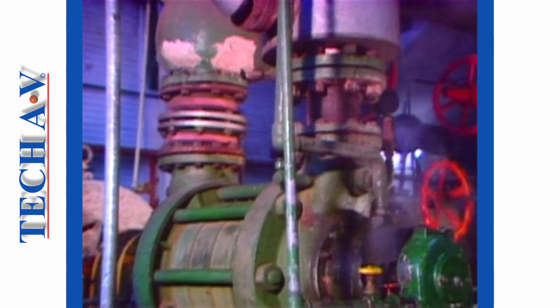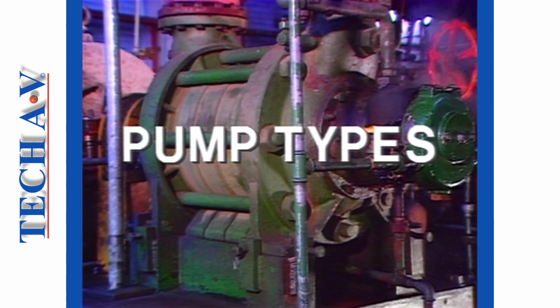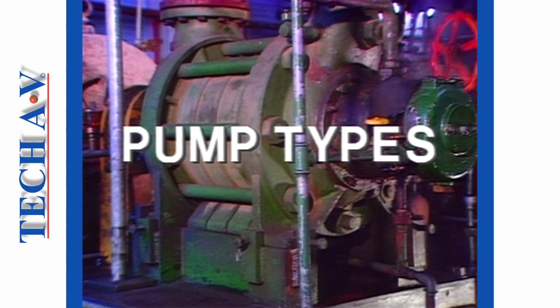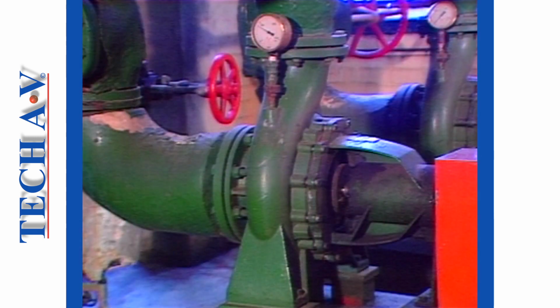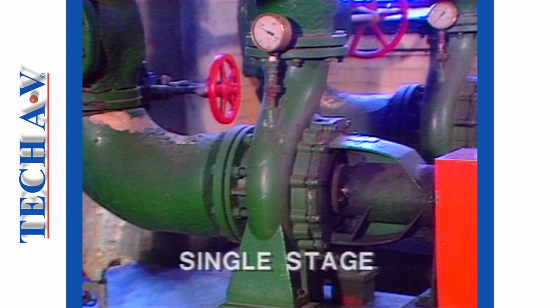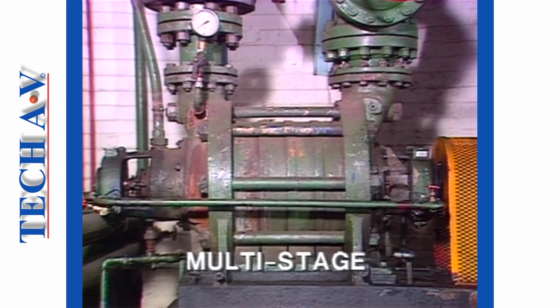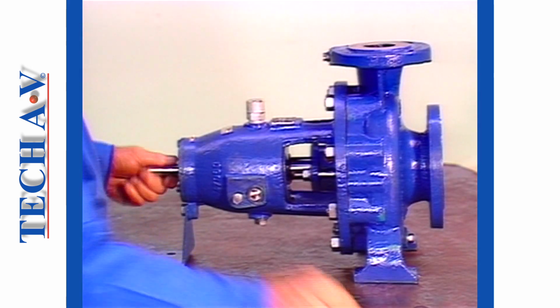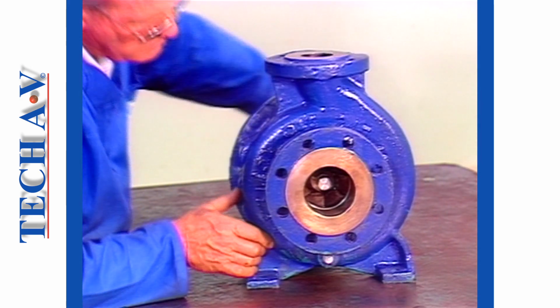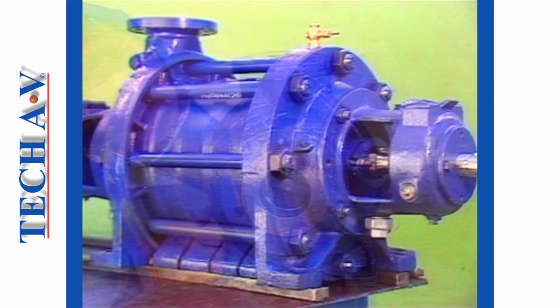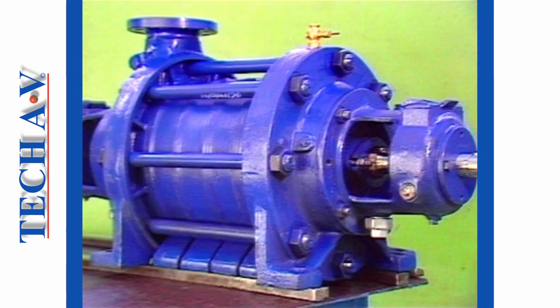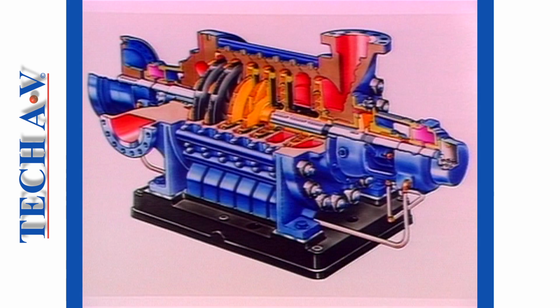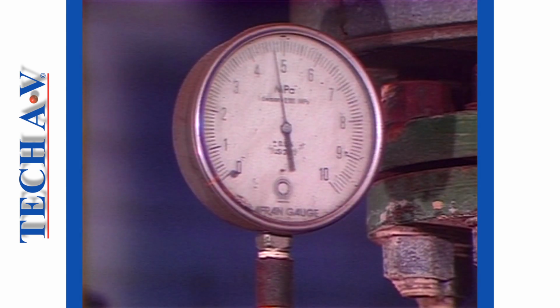We return to discuss some of the centrifugal pump types that you are likely to encounter in general industrial areas. To make a general categorization, there are two main classifications of centrifugal pumps, namely single stage and multi-stage. A single-stage pump comprises one hydraulic section, that is, one impeller and one casing, whereas a multi-stage comprises two or more hydraulic sections, usually arranged one behind the other. A common shaft drives all the impellers.